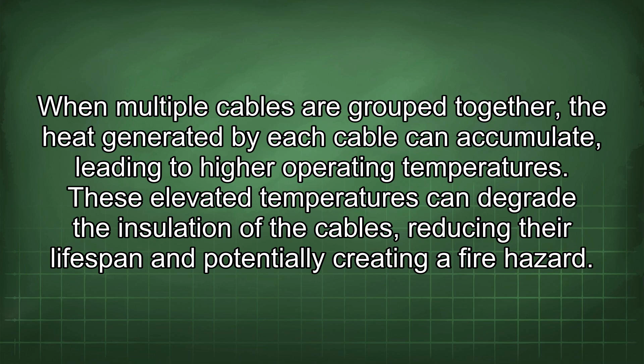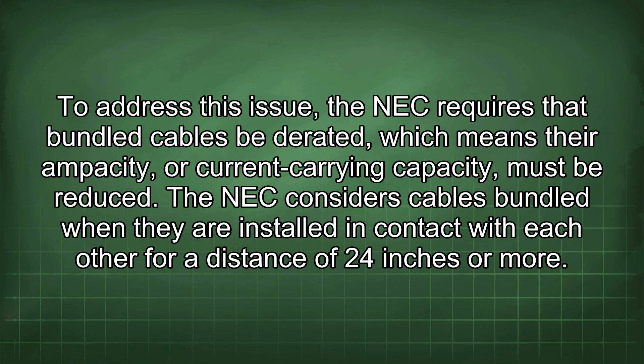These elevated temperatures can degrade the insulation of the cables, reducing their lifespan and potentially creating a fire hazard. To address this issue, the NEC requires that bundled cables be derated, which means their ampacity, or current carrying capacity, must be reduced. The NEC considers cables bundled when they are installed in contact with each other for a distance of 24 inches or more.